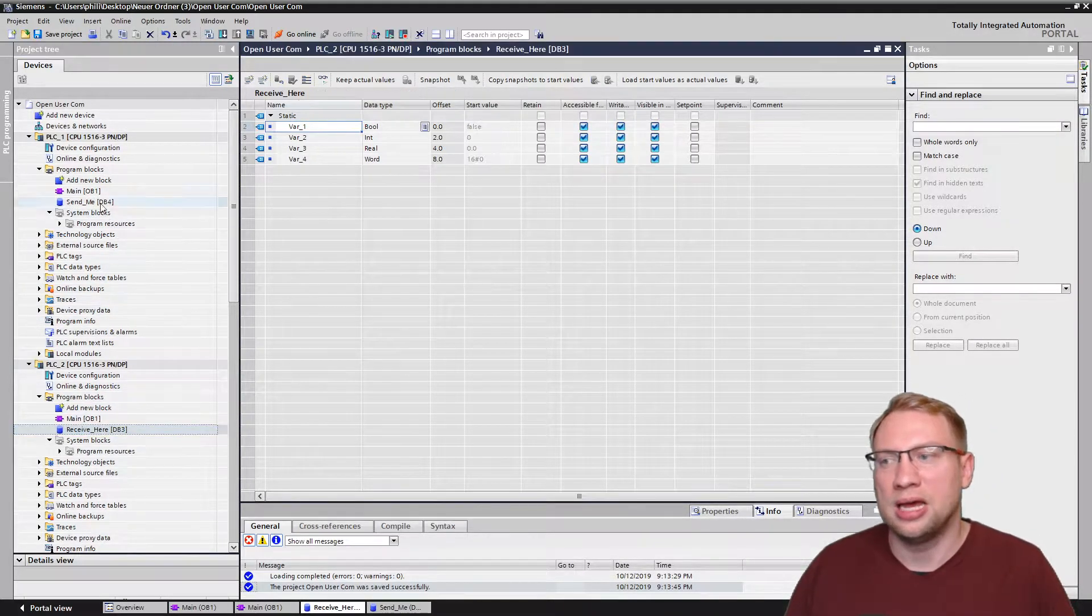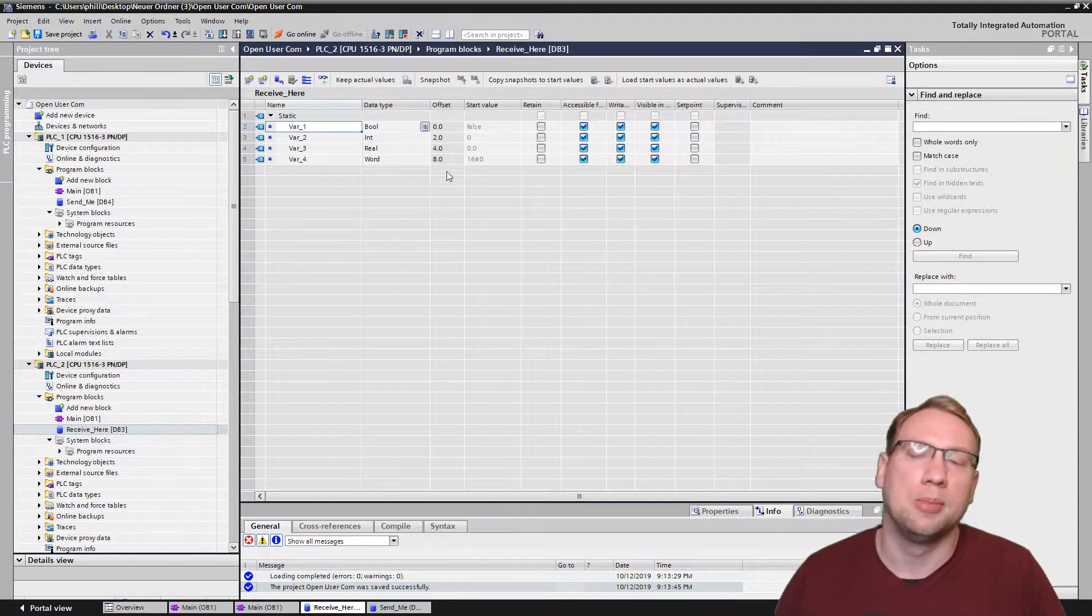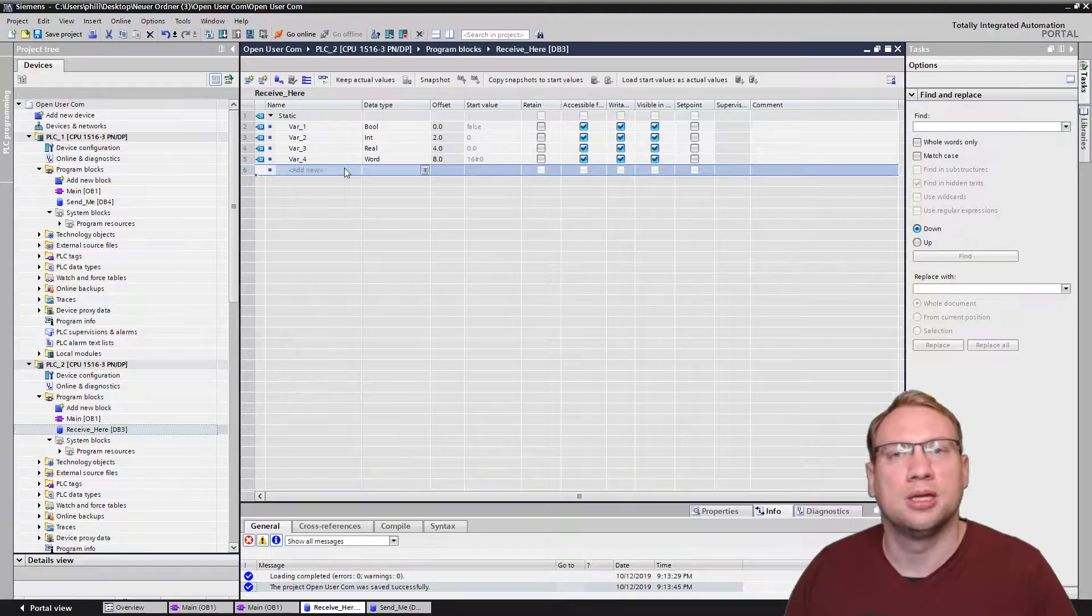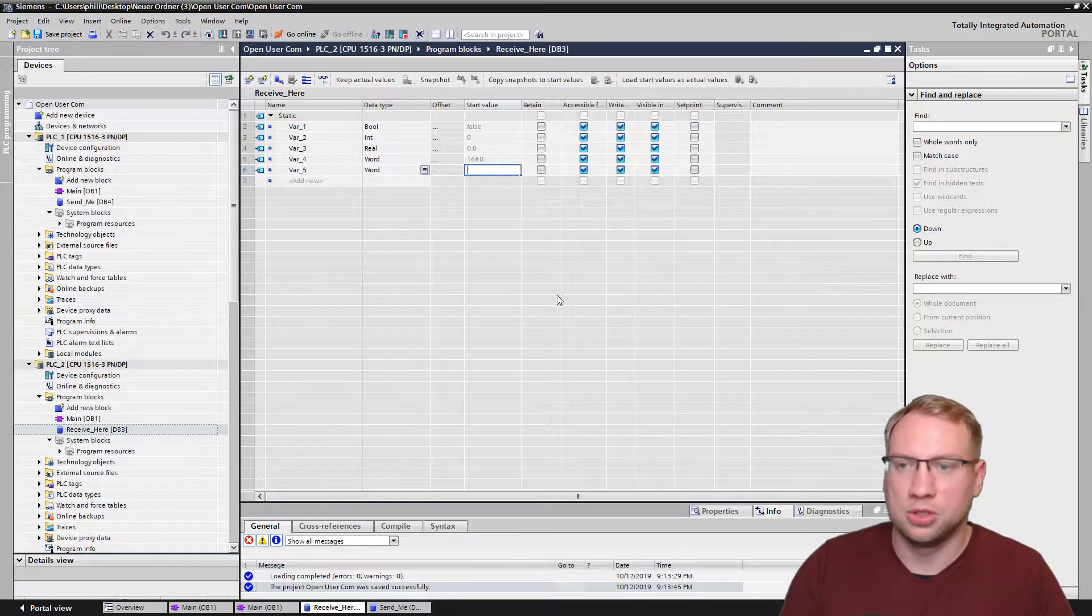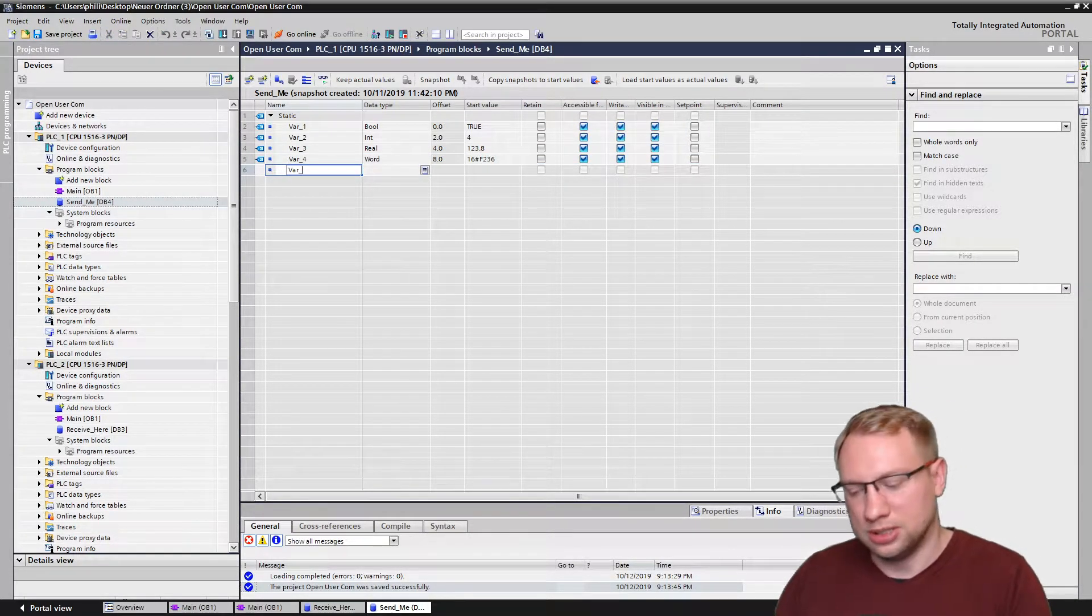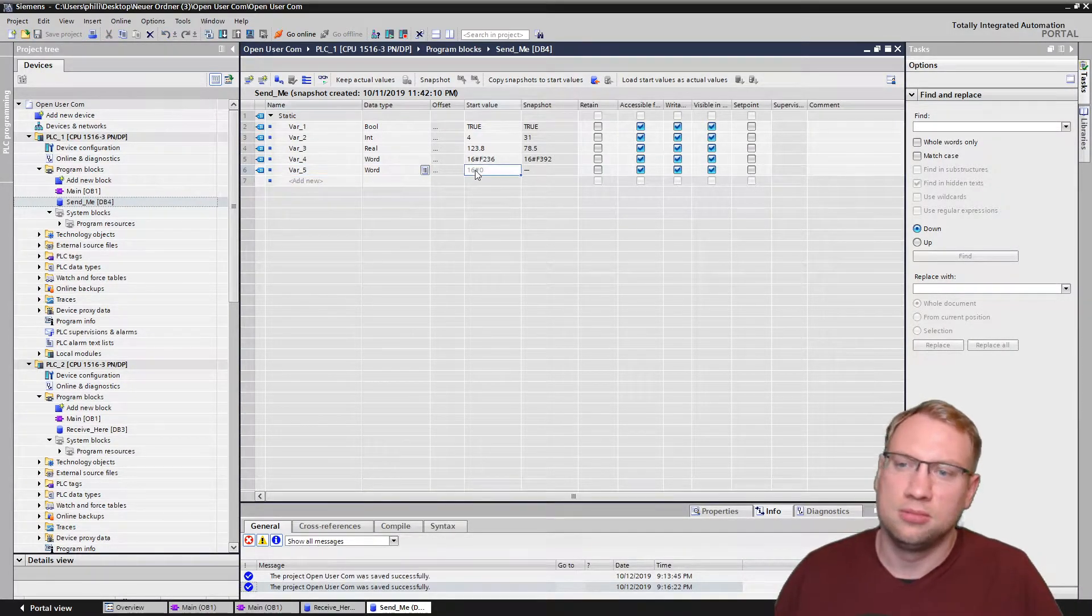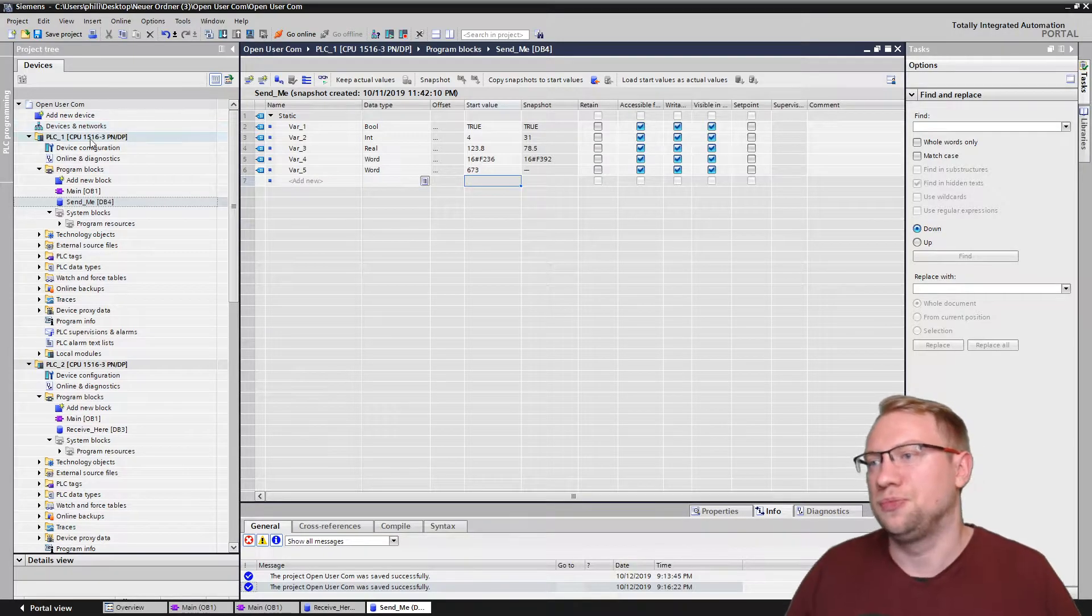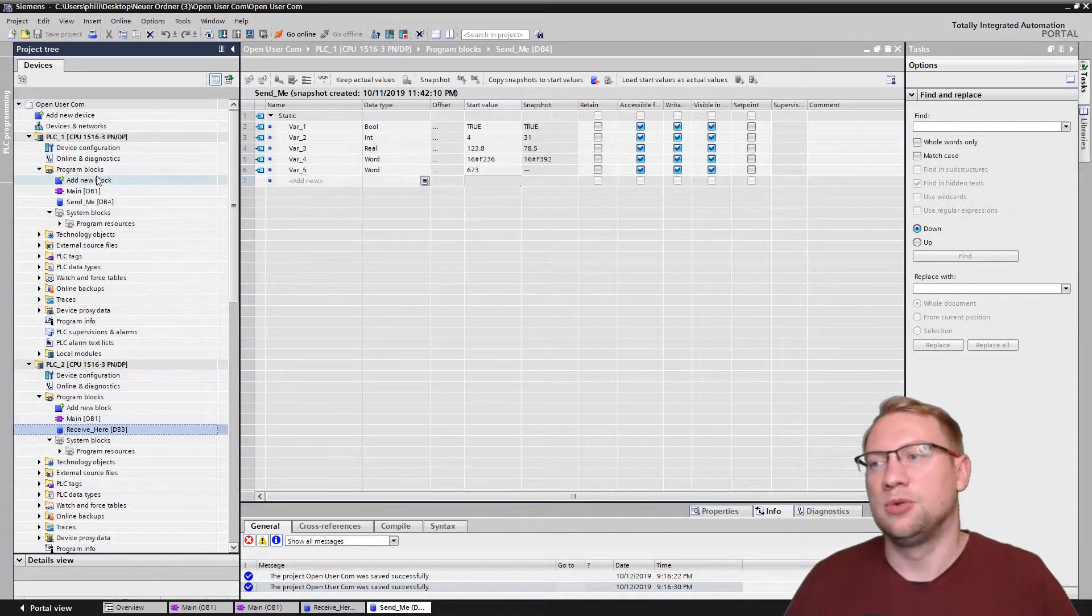Make sure that those have the same layout. You see, I have one boolean, one int, one real, one word value that I want to send, and I have the same structure on the other PLC. If I want to add more, we can always add more, but then make sure that you do that on both sides. I also want to do that on the other side. You can add many, many more. I think 80,000 or so is the limit. And they don't even need to have the same name. I always keep it like that because it's just easier for me to remember. I want to send this data block and put it into the receive data block.